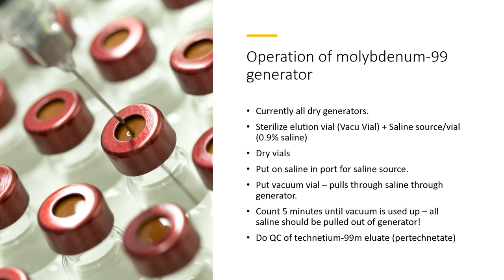Currently all molybdenum generators are dry. You use a dry vacuum vial, put saline in, push it through, and count five minutes until all the vacuum is used up, making sure all the saline is removed. It is generally best to put on your vacuum vial, connect your saline, let it pull all the saline through, and then wait an additional five minutes to make sure it's dry. If you have problems with your generator, most often placing another vacuum vial on and drying it again will solve the issue.